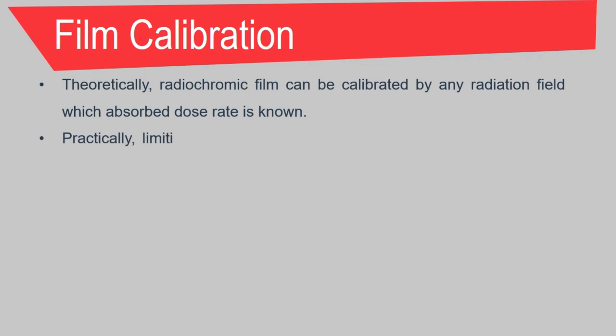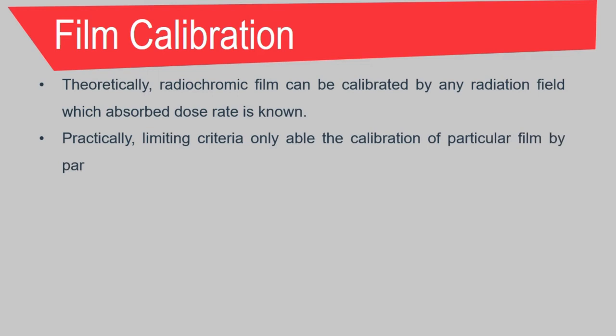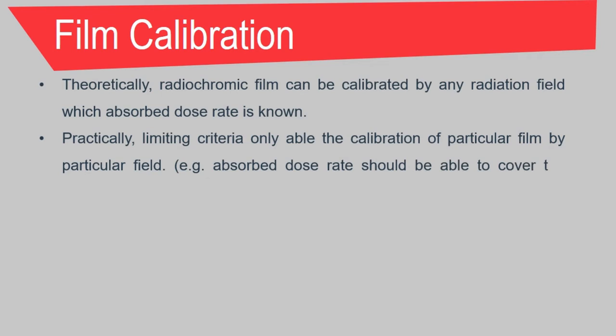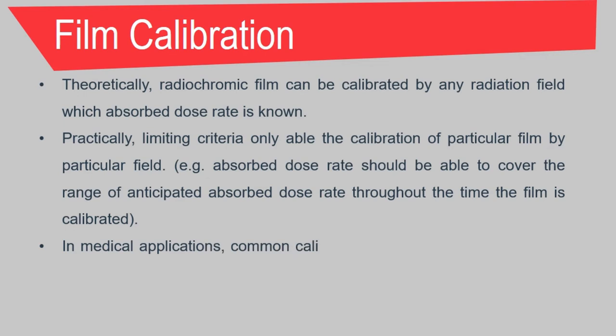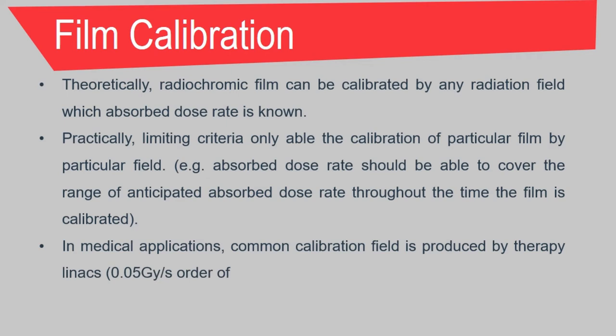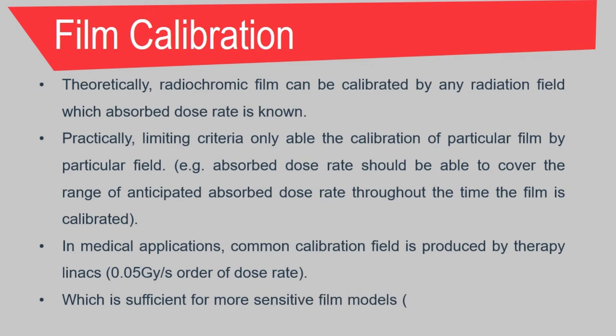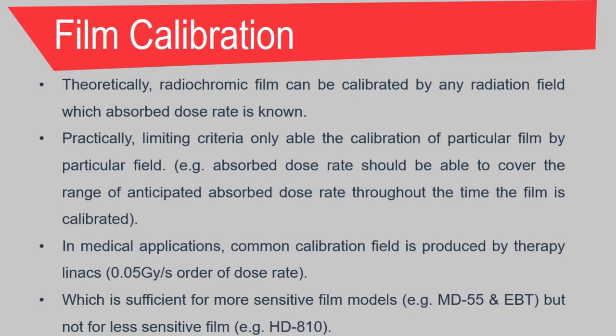In film calibration, theoretically, radiochromic film can be calibrated by any radiation field for which the dose is known. However, practically, limiting criteria only allow calibration of a particular film by a particular field. For example, the absorbed dose should cover the range of anticipated absorbed dose throughout the time the film is calibrated. In medical applications, the common calibration field is produced by a therapy linac, with the order of dose being 0.05 Gy per second. This dose level is sufficient for more sensitive film models such as MD-55 and EBT, but not for less sensitive films such as HD-810.